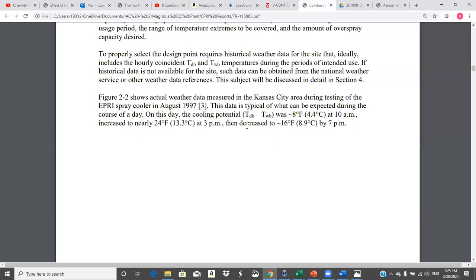So let's say the air was 90 degrees and the difference between those was, let's say, 10 degrees, then you could get 8.8 degrees taken away from the 90. And so you could be at what, 81.2 degrees. And then you've got to look at the performance of your gas turbine, say for that hour, if you have hourly data, to see how much enhanced power you're going to get out. And you can also look at what happens to the heat rate, because that's going to tell you how much additional fuel you may have to put in. Okay, so that's kind of the way this game gets played.